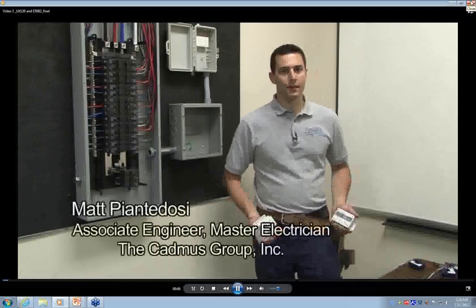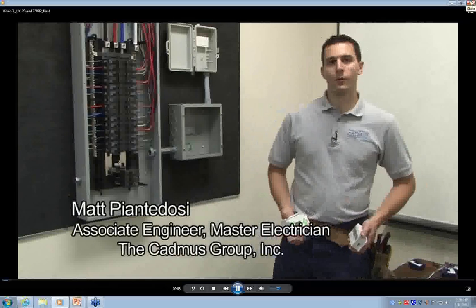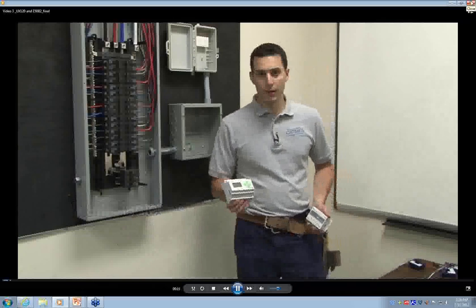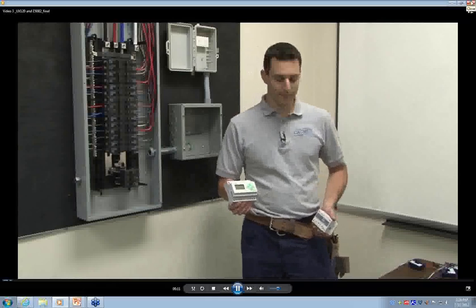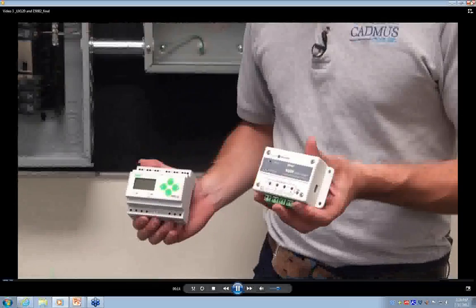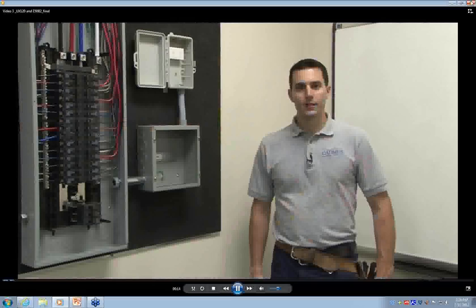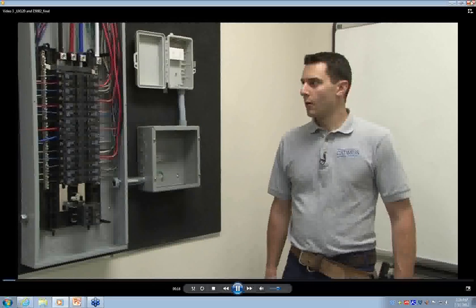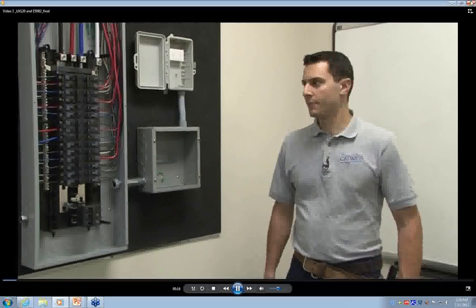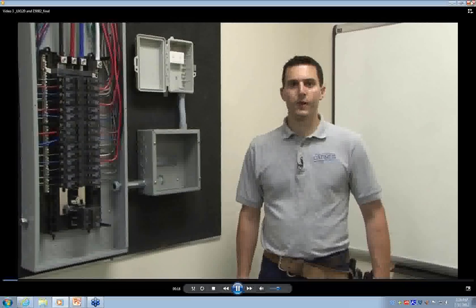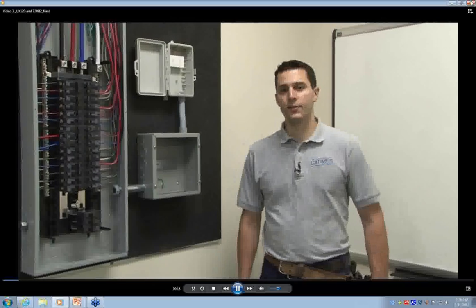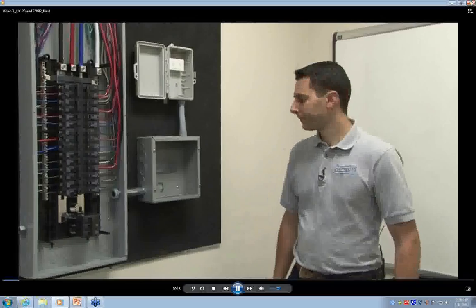We'll now install a data logger to monitor the whole panel power. We'll do so by using an Onset E50B2 power meter and an Onset HOBO UX120. Since this will be a permanent installation, we want to make sure that we safely de-energize the panel board that we're working in. We follow the lockout-tagout process as described in NFPA 70E.